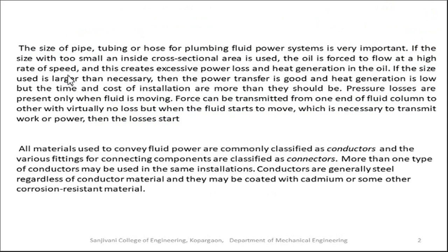So the size of pipe which you are going to use in the fluid power application is very critical. If the size is less than necessary, then the oil has to be forced through a constricted cross sectional area that will cause a high amount of friction and heat generation. Because of that, energy is lost due to the heat generation.